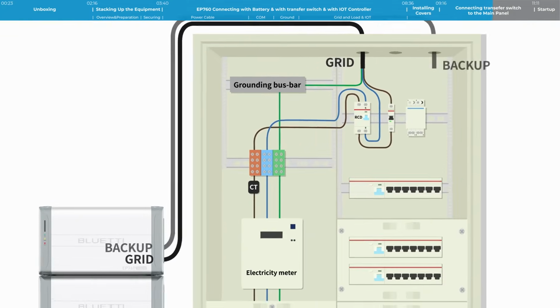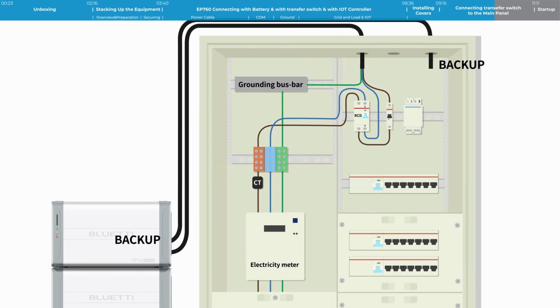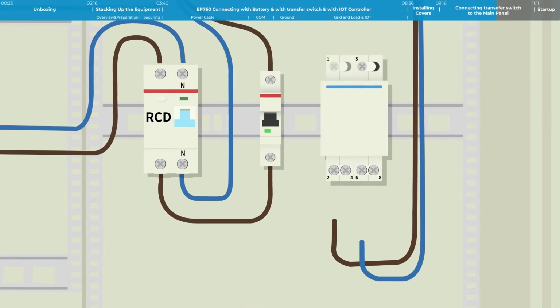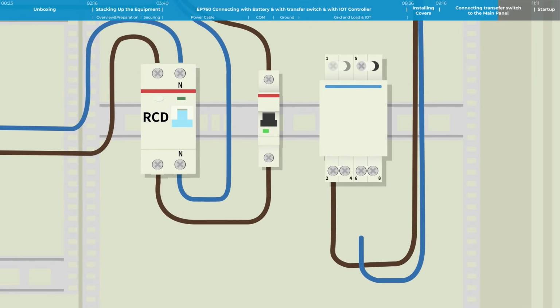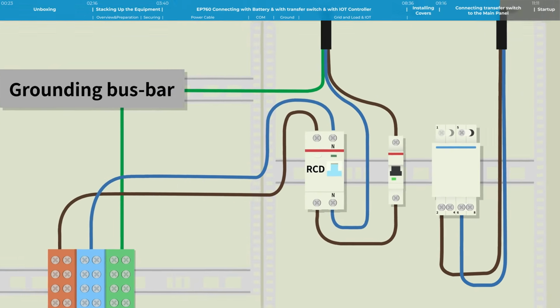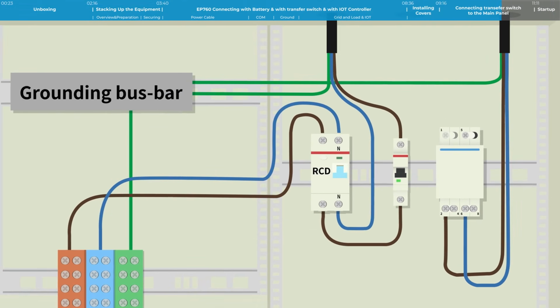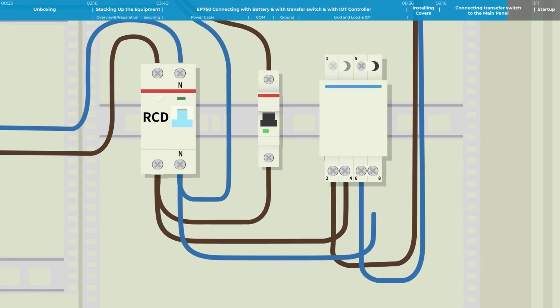Connect the EP760's BACKUP cable to the 2P transfer switch terminals. L to pin 2, N to pin 6. Connect the PE cable to the PE busbar. Then, connect one live wire and one neutral wire from the 2P RCD terminal to the 4, 8, N terminal of the 2P transfer switch, L to pin 4, N to pin 8.